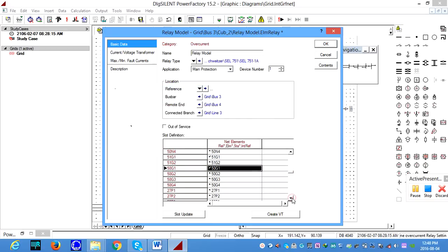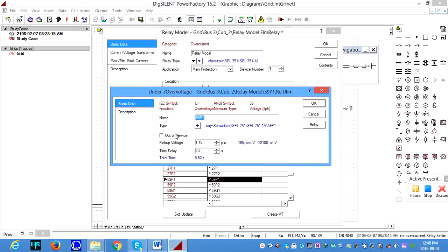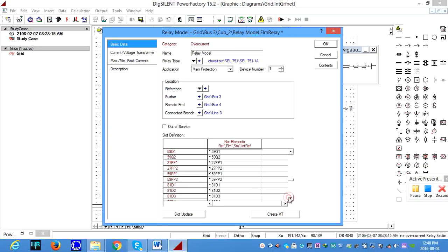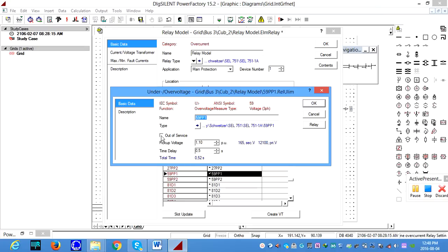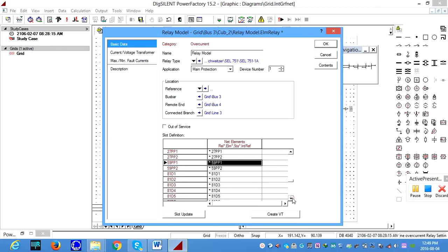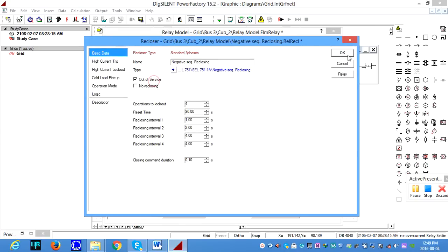Okay, happy about that. And this 59P1, okay, this is over voltage measurement, that is out of service. We're not focusing on over voltage, and also over voltage for the ground elements we're not interested in. Stage 2 ground element for over voltage, make sure it is out of service. 59PP, okay, this is also out of service. So we make sure everything that is supposed to be out of service is, because as I told you, this is a multifunctional feeder protection relay, but we are basically looking only at the overcurrent element. And also phase reclosing, we are not interested. Negative sequence reclosing, we are not interested. So we make sure it is out of service. Neutral reclosing, out of service. Ground reclosing, all the reclosing must be out of service.